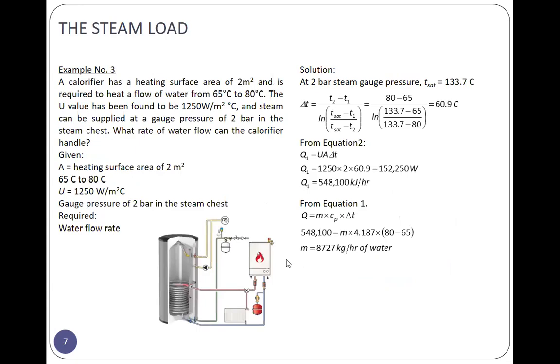So, example number 3. So this is now case 2. A calorifier has a heating surface area of 2 square meter. This is not case 2. What is this? The heat transfer. And it is required to heat a flow of water from 65 to 80 C. The U value has been found to be 1250 watt per square meter C.